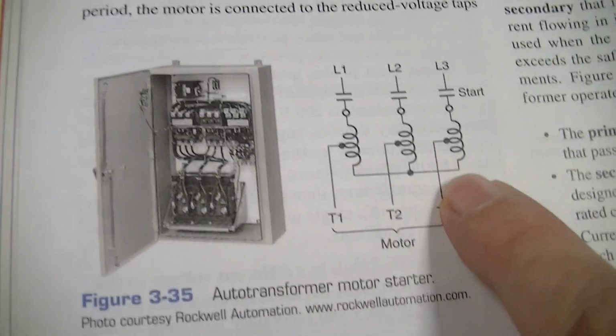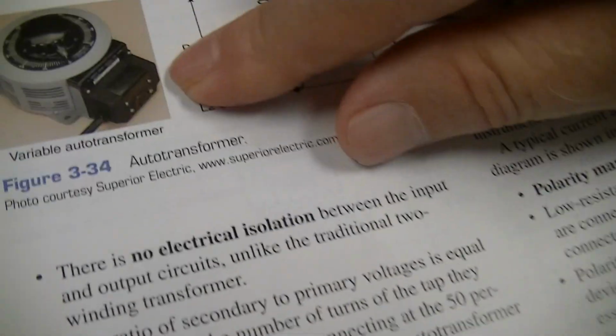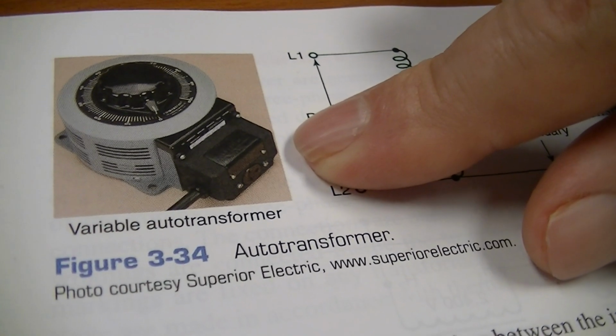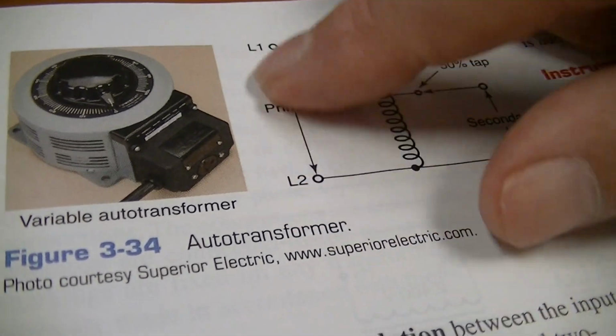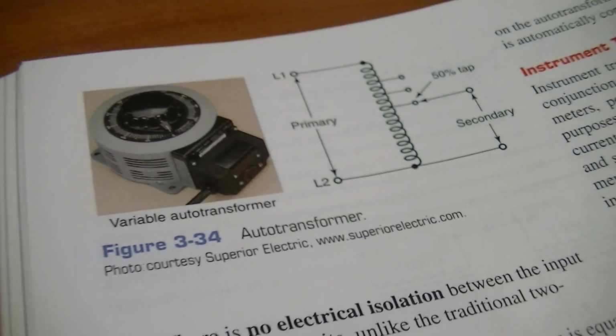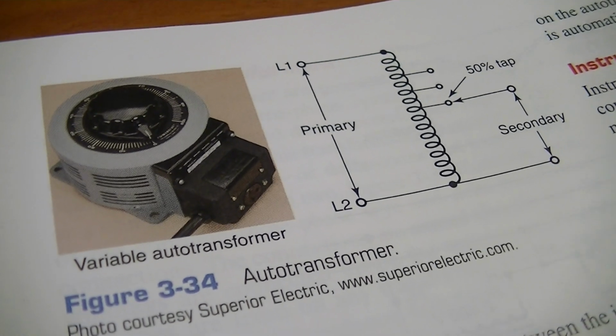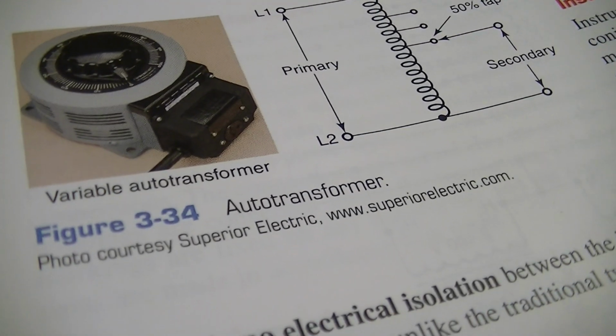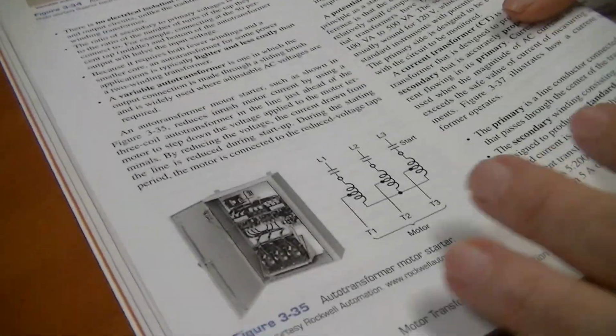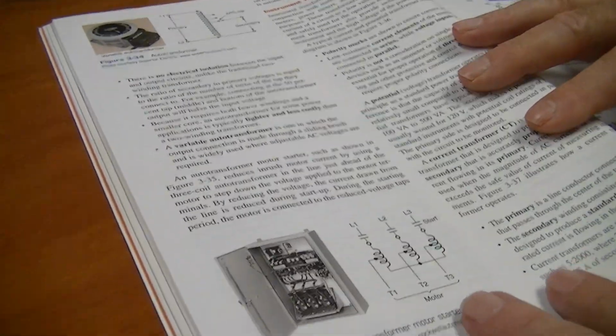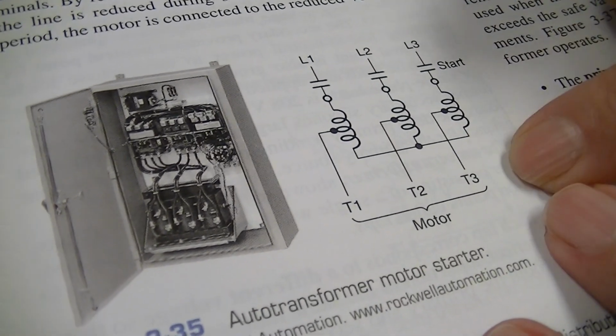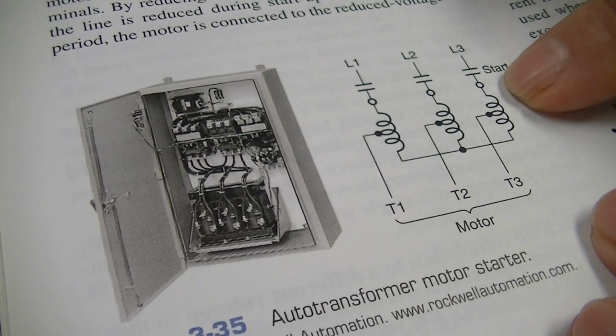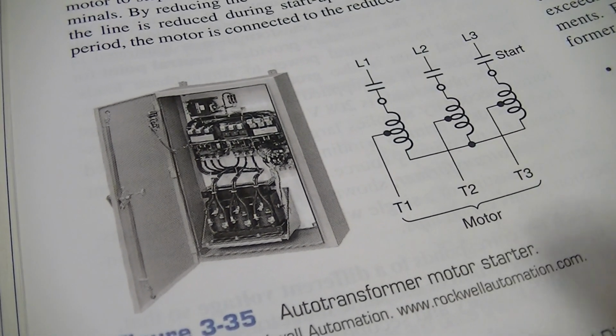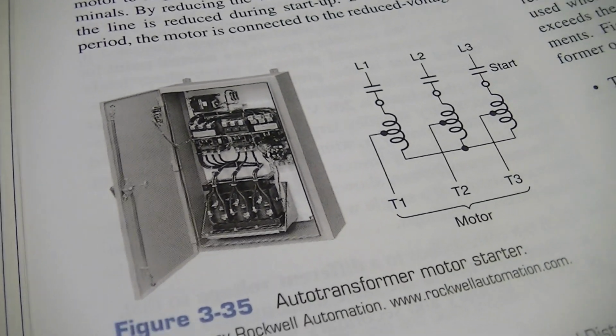Okay, and then so this would be a three-phase. Okay, this first one up here, what we call in the industry, we call it a Variac. Okay, because we can vary the voltage from 0 to whatever the maximum is. The one I've got here, even though you plug it into 120 volts, I can actually get it up to the point that by tapping past that upper tap, I can get 150 volts out of it. So, believe it or not, there's different ways of skinning the same cat. Then a three-phase, again, you could use that to vary the voltage, starting up a motor. You could have something that's ramping up and automatically raising the voltage as you try to start a motor.